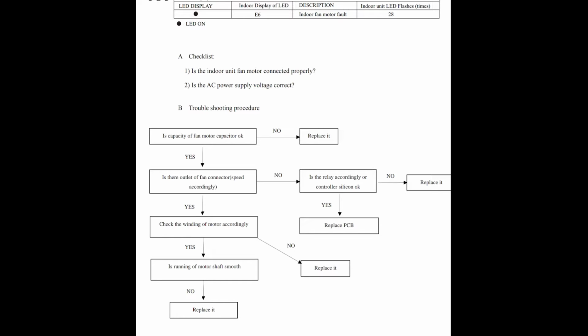So how do we read this? How do we go through this? When I get to the call, the indoor unit is going to display an E6, and that error code has a description of indoor fan motor fault. So we know that the indoor fan motor is the issue, or it's to do with the indoor fan motor.